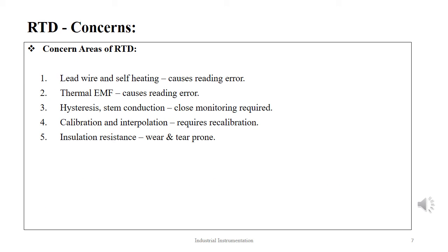There are few areas of concern associated with the RTD which require close and timely monitoring, and these areas are lead wire and self-heating induced in it. Development of thermal EMF, the sensor's stability, repeatability, hysteresis, and stem conduction should be checked at a timely interval. The calibration and the interpolation are also changed and therefore they should be recalibrated. The insulation resistance is prone to wear and tear and therefore calls for proper and timely maintenance.